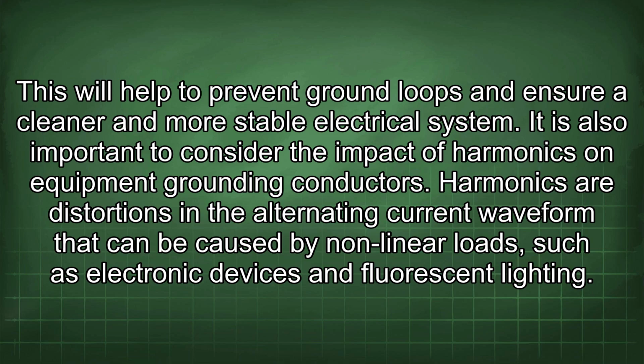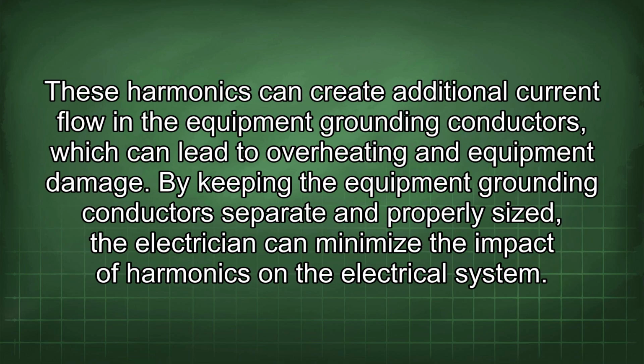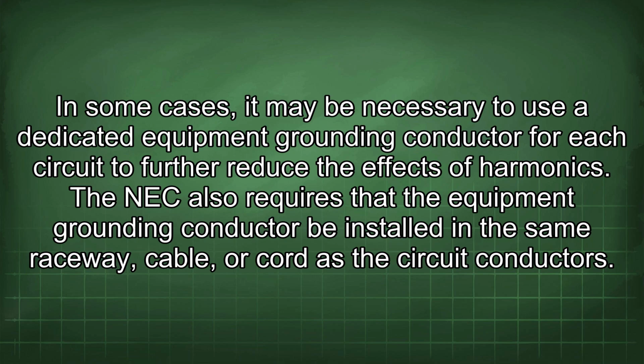It is also important to consider the impact of harmonics on equipment grounding conductors. Harmonics are distortions in the alternating current waveform that can be caused by nonlinear loads such as electronic devices and fluorescent lighting. These harmonics can create additional current flow in the equipment grounding conductors, which can lead to overheating and equipment damage. By keeping the equipment grounding conductors separate and properly sized, the electrician can minimize the impact of harmonics on the electrical system. In some cases, it may be necessary to use a dedicated equipment grounding conductor for each circuit to further reduce the effects of harmonics.